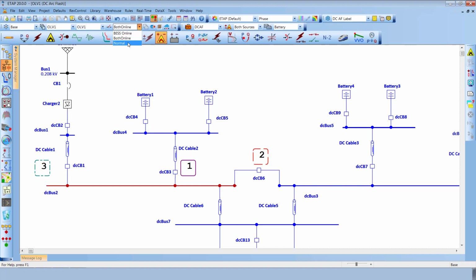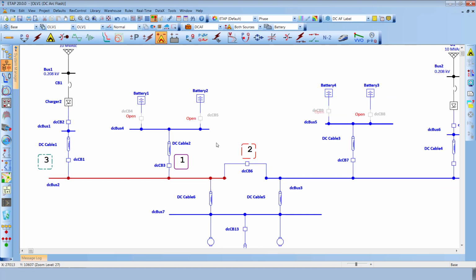In this project, I have created 3 different configurations, starting with the normal configuration where the utility is feeding the system on the DC side through a rectifier or a charger, in the same condition where the batteries are assumed to be in the charging mode. The state of discharge starts when the battery system energy storage is starting to release energy when a loss of utility condition has occurred. And there is the third configuration where both sources are set to be online and the incident energy evaluation is performed accordingly.